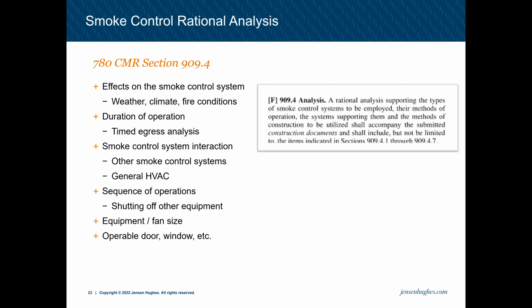Smoke control rational analyses have to detail the effect of a smoke control system. So that's the weather, climate, or maybe fire conditions that might have on the system. For stair pressurization, that's relatively straightforward, but for an atrium exhaust system, it gets much more complicated.